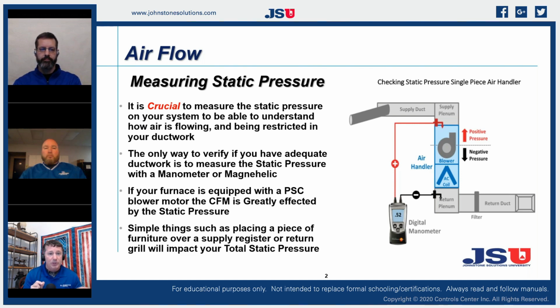We would actually have to put a secondary port in that air handler to be able to read the true pressure from the coil through the blower, not including that filter. So that's a big misconception in the field.